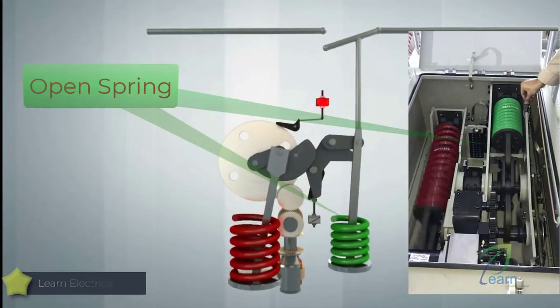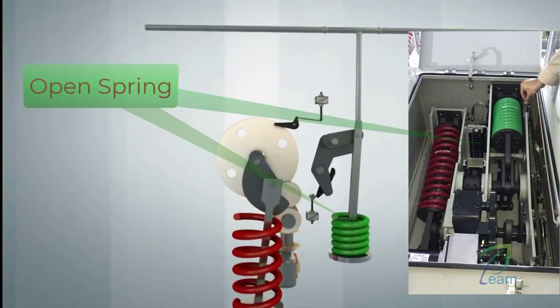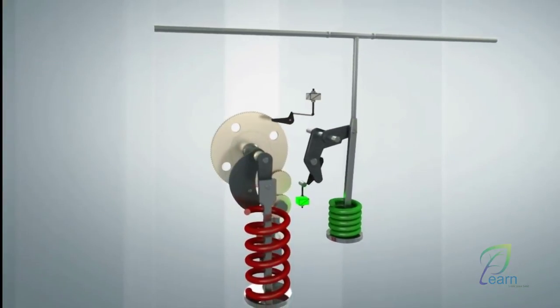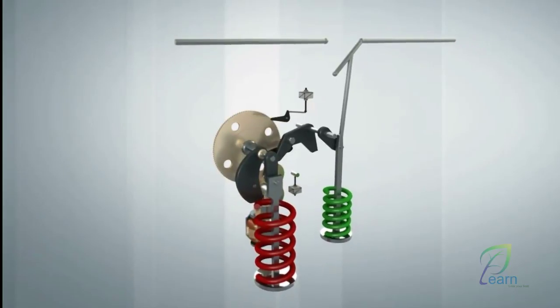The springs are charged by an electric motor. As the opening spring is generally charged through the closing spring, the circuit breaker can always be safely tripped even if the auxiliary power supply fails.